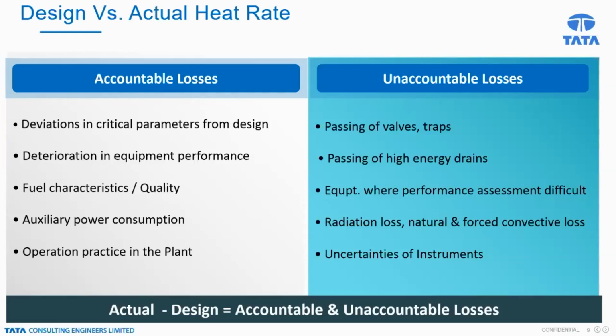Then the fuel characteristics are also important. Though we designed the boiler for certain specified fuel qualities and characteristics, in actual operation we will be burning different types of fuel because of availability and also based on the cost of fuel. Based on the difference in fuel characteristics, the boiler efficiency would be different, and accordingly the heat rate would be different. Then auxiliary power consumption: we would be operating some of the standby equipment, or the degradation of pumps, fans or compressors can cause higher auxiliary power consumption during the operating period. Operating practice of the plant, how we are operating and maintaining the various systems and equipment, will also have an effect.